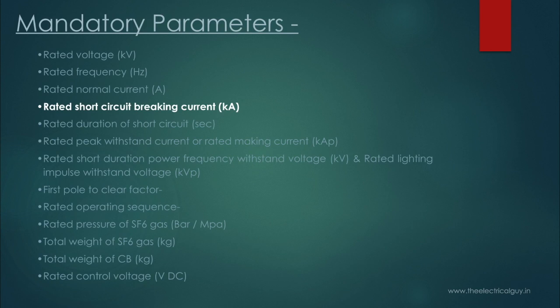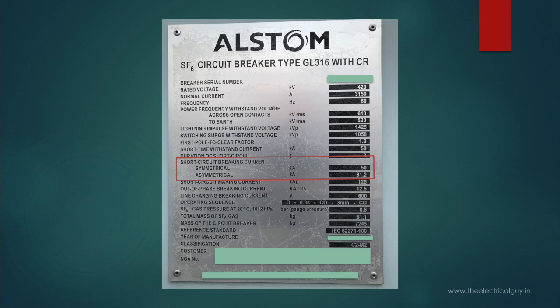Next is rated short circuit breaking current — the highest RMS value of short circuit current which the circuit breaker is capable of breaking, given in kiloampere RMS. It is sometimes also called symmetrical breaking current. On some nameplates you will find short circuit current given as both symmetrical and asymmetrical current. Symmetrical current is the AC component, equal to the rated short circuit current, whereas asymmetrical current is the combination of AC and DC components, and is therefore greater. So 61.2 kA is the actual amount of current this circuit breaker can break.